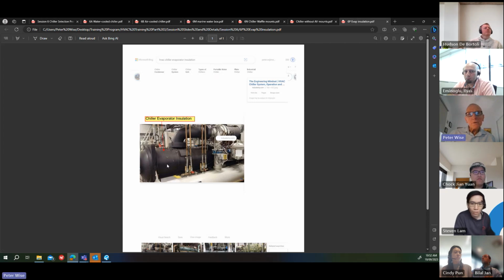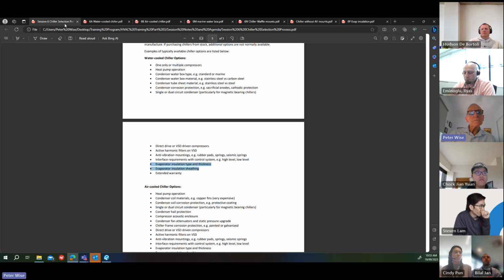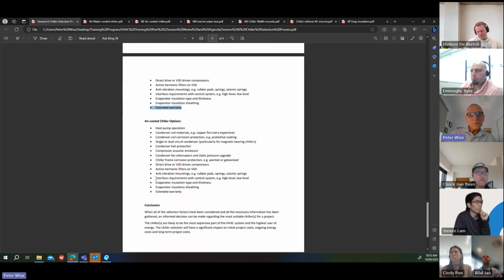So if you want to give that extra protection for the plant room, or if it's outside, they can sheathe that using metal sheathing, might be Colorbond or just galvanised steel sheathing, as you would for chilled water pipe. And as I said before, you can request extended warranty. They usually give you a warranty up to 5 years, but at significant additional cost.